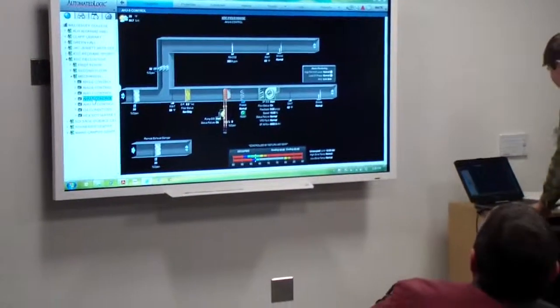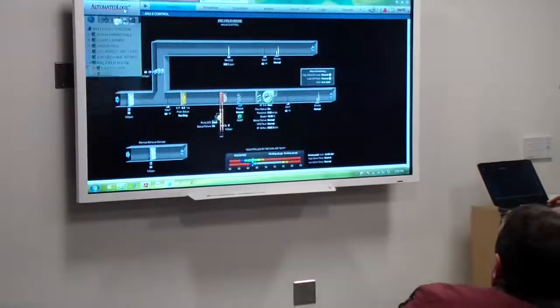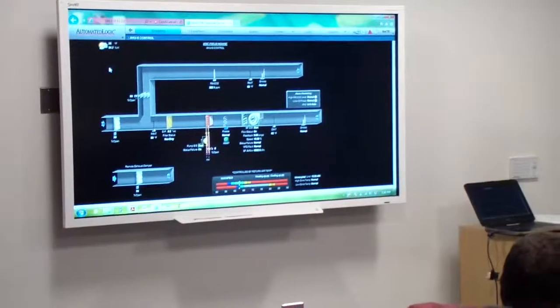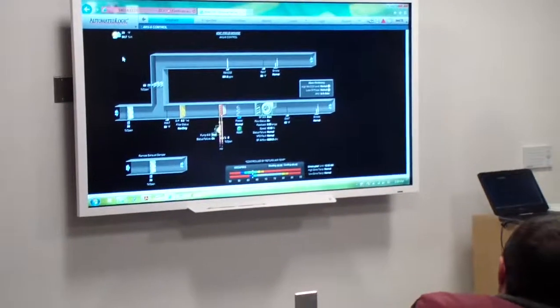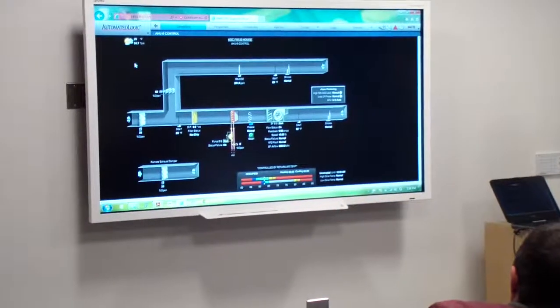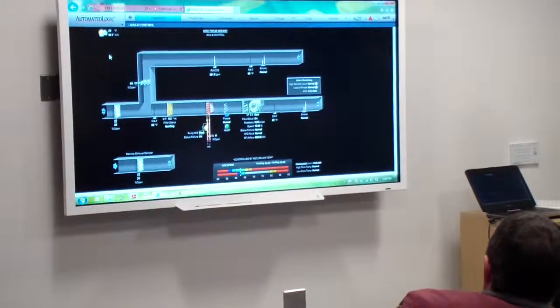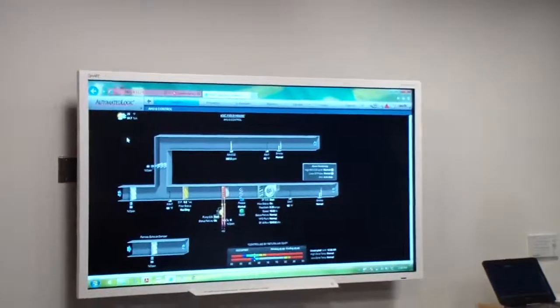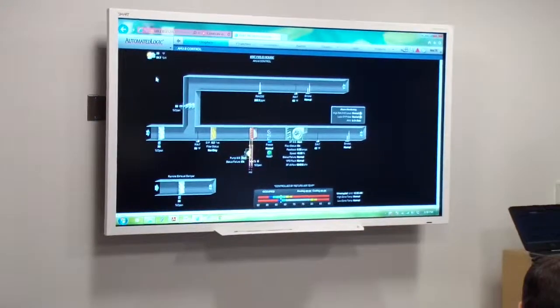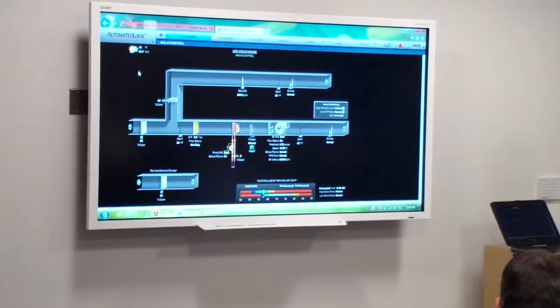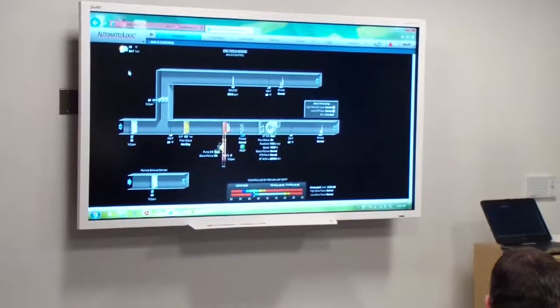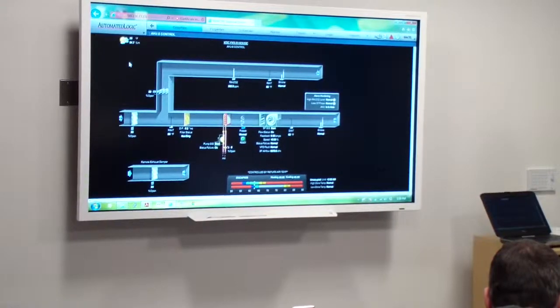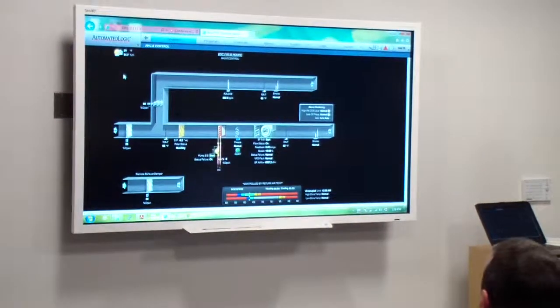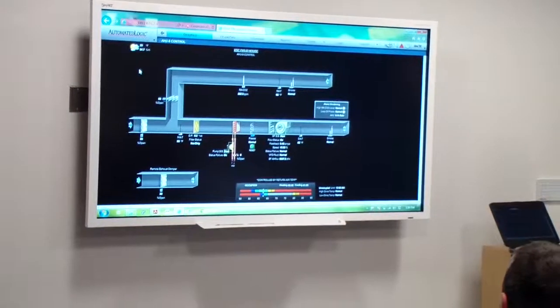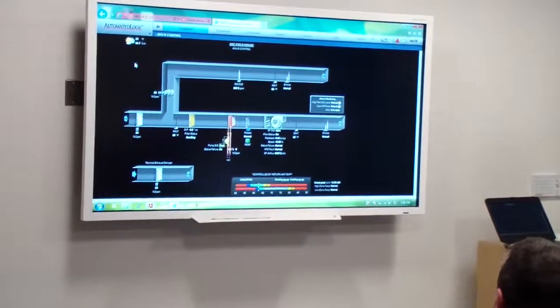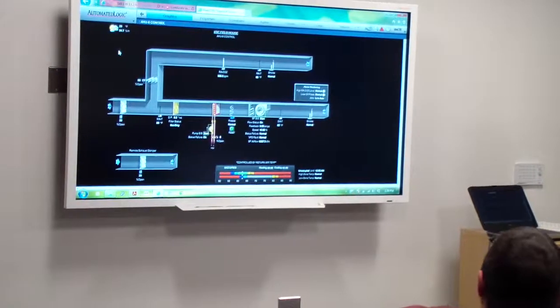And lastly, far back by the garage doors is HE8. I'll follow up with that too, as part of our project, our scope of work on those old units was to come in and clean the ductwork. So during construction, the units were shut off. The return air plenums were taped off with a filter fabric to prevent anything from going up there. And then once we had the bulk of the construction work done, we had hired a company that came in through Pinnacle, a duct cleaning service. They came in, cleaned all the ductwork, refiltered them, and then, like I said, Pinnacle's actually got more filters just to give you guys a fresh, brand new set.